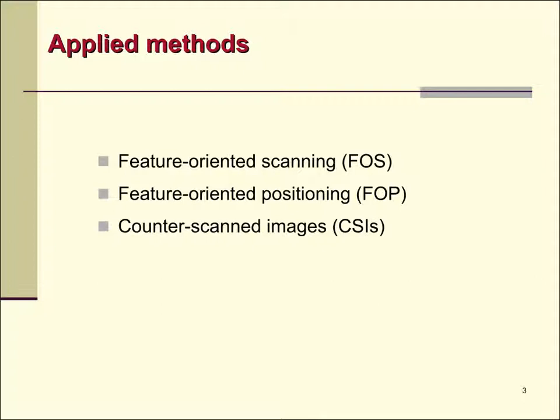Applied Methods: To eliminate the negative influence of noise, thermal drift and creep upon the distributed calibration results, the following methods were used: Feature Oriented Scanning, Feature Oriented Positioning, and Counter Scanned Images.